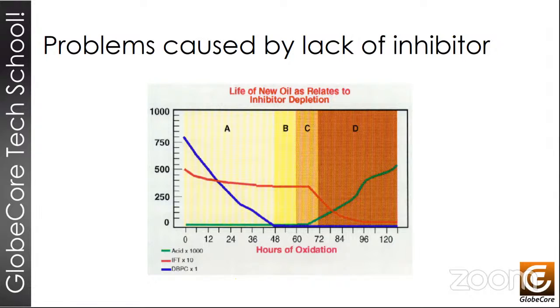The point of analysis for an oxidation inhibitor is on this blue line, and you will see where it hits 0. So as long as we can determine that it's decreasing, we can add inhibitor and fix it. And basically, it's an indication of sorts.